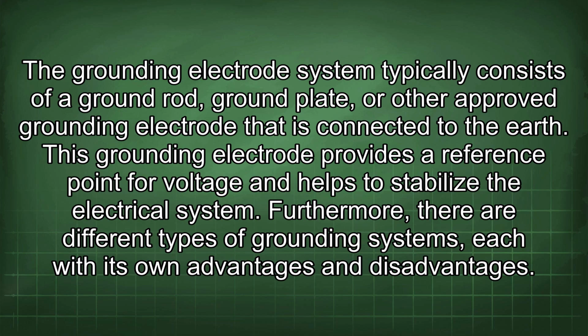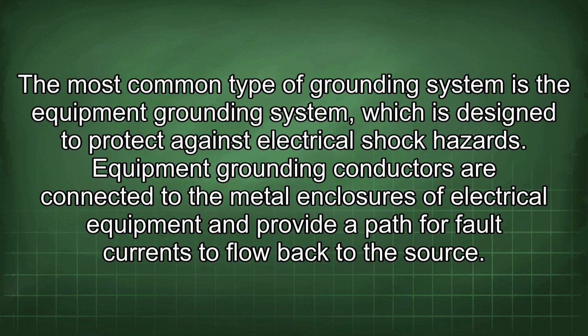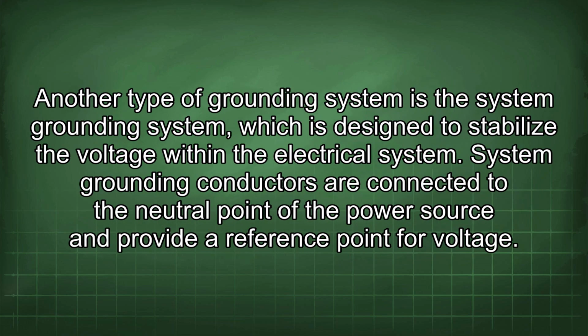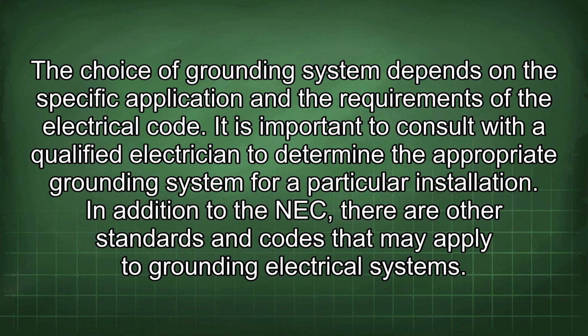Furthermore, there are different types of grounding systems, each with its own advantages and disadvantages. The most common type of grounding system is the equipment grounding system, which is designed to protect against electrical shock hazards. Equipment grounding conductors are connected to the metal enclosures of electrical equipment and provide a path for fault currents to flow back to the source. Another type of grounding system is the system grounding system, which is designed to stabilize the voltage within the electrical system. System grounding conductors are connected to the neutral point of the power source and provide a reference point for voltage. The choice of grounding system depends on the specific application and the requirements of the electrical code.